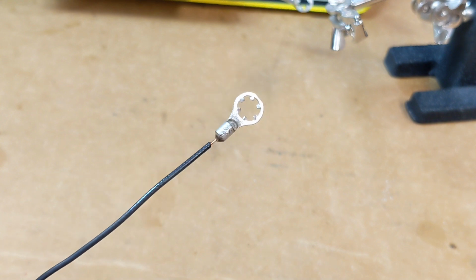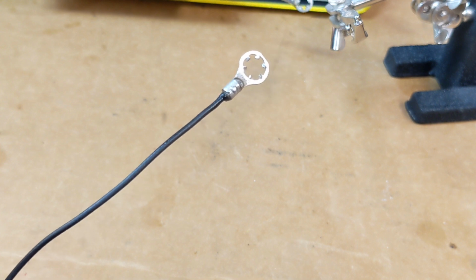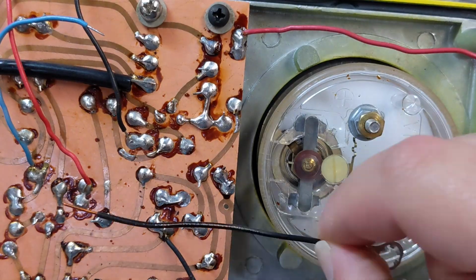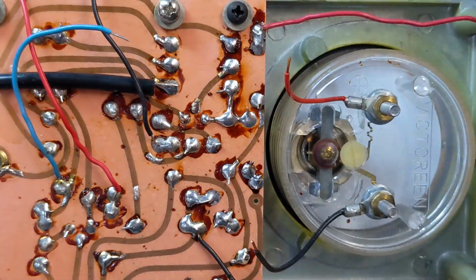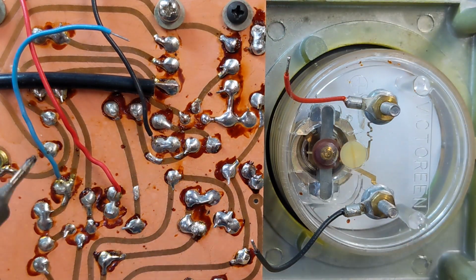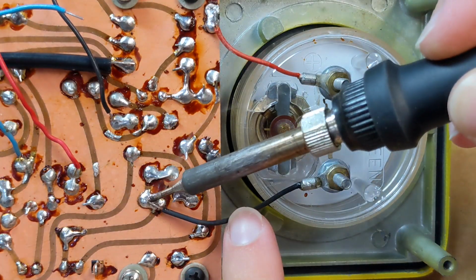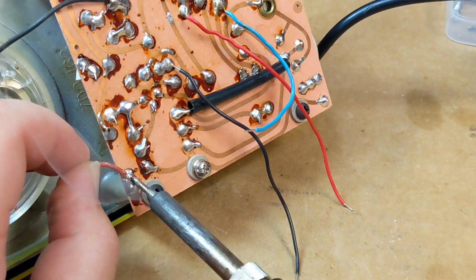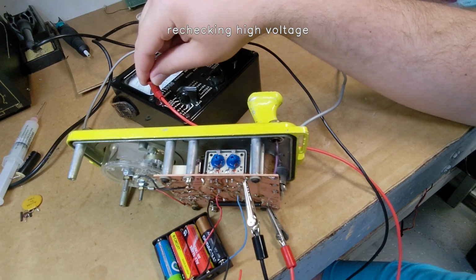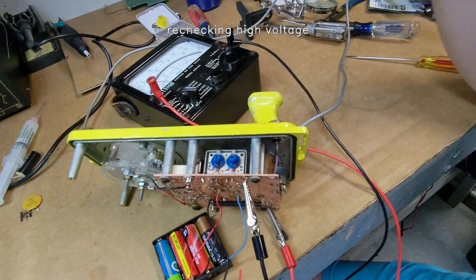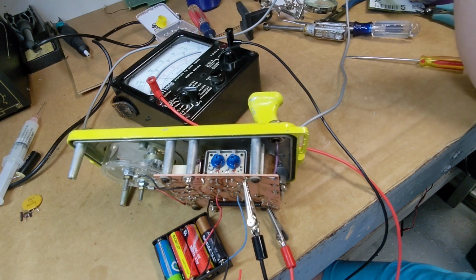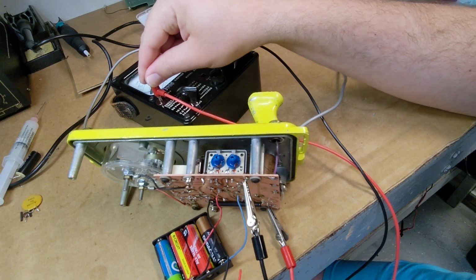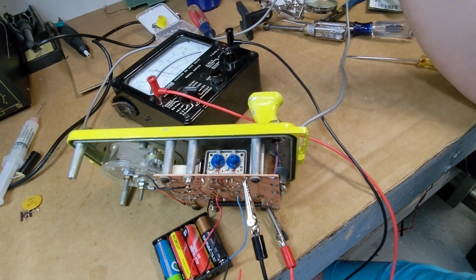Too much wire on the end? No, there isn't. I think the meter is loading it down on startup. So I shut it down, turn it on. It only gets to there, but then I disconnect the meter and reconnect it a couple times maybe. Yep, and there it is at the 900 volts it's supposed to be on.